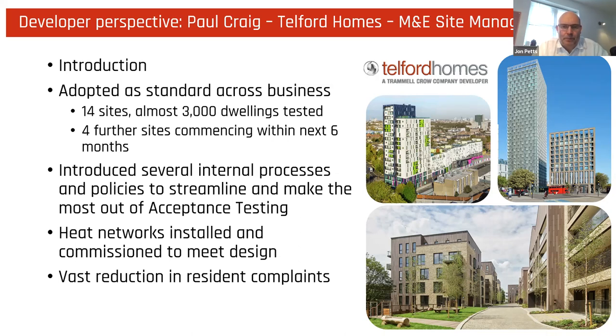As you probably picked up on some of the other discussions throughout the day, we only need a small amount of bypass on an HIU for the network to go down, and otherwise all the commissioning within the flat is picking up loads of little details, which individually may be quite small, but they do all have a knock-on effect to the wider network. Yes, it is a time-consuming exercise, and yes, it happens at a fairly critical time, normally, hopefully, in the weeks before handover, not the day before.